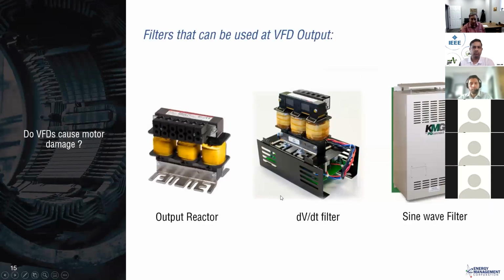Well, what I'm showing here is that an output reactor, and probably not just any output reactor, can also, in the right situation, substantially mitigate some of this phenomenon in certain applications. So we look at this as kind of a stepped approach. You've got an output reactor, a dV/dt filter, and then a full sine wave filter. A good place for a sine wave filter: we probably would not install a deep well submersible pump without an output sine wave filter. It's just too expensive to pull that pump out of the hole for a dV/dt failure.